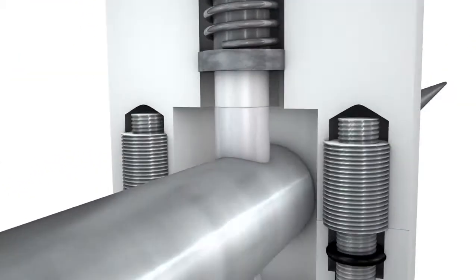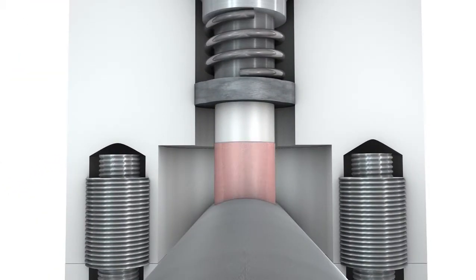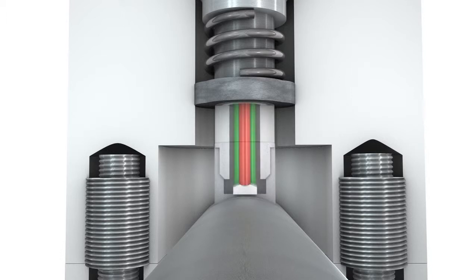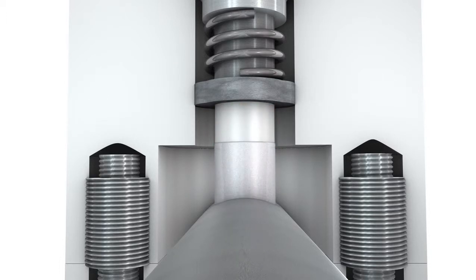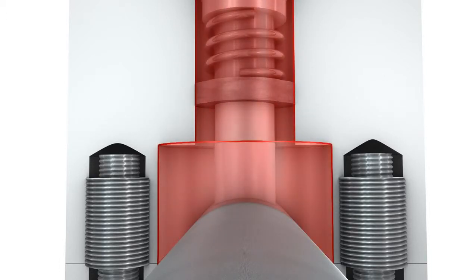This is how the measuring insert looks from the inside. The temperature sensor consists of a silver tip shaped to fit the pipe. The PT100 element is situated as close as possible on top of the pipe. Silver is used here because of its excellent heat transfer properties. A plastic element provides thermal insulation. It prevents measurements from being corrupted by heat dissipation. An air cushion provides additional insulation at the temperature pickup point.